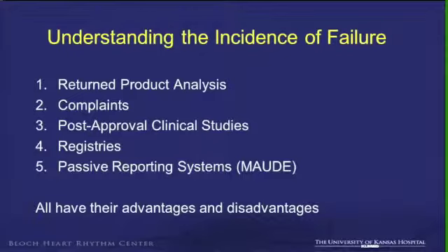Post-approval clinical studies are probably the best, but they're very expensive. These days, FDA has mandated many new devices to undergo approval studies. Some are FDA mandated, some are industry mandated, but you do have these increasing. Registries have their observational limitations. Passive reporting systems are a free press. You can put what you want, but the authenticity of the device reporting is not very accurate, even though till now we've made reasonable advances in identifying some early failures using the MAUDE database.